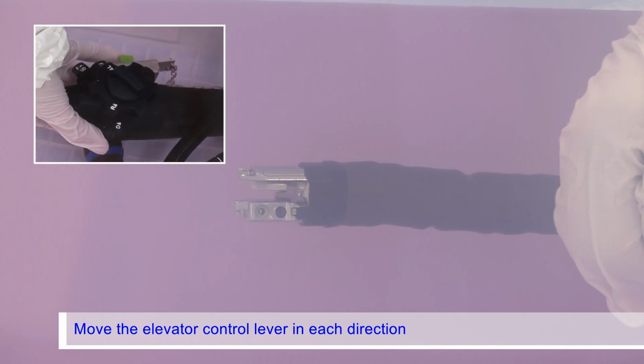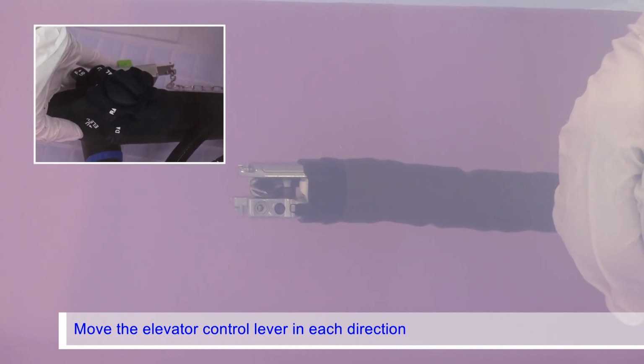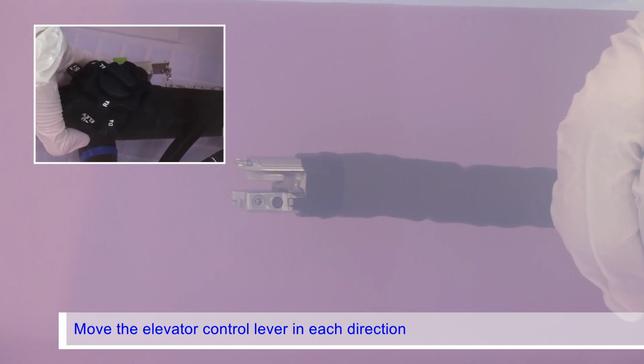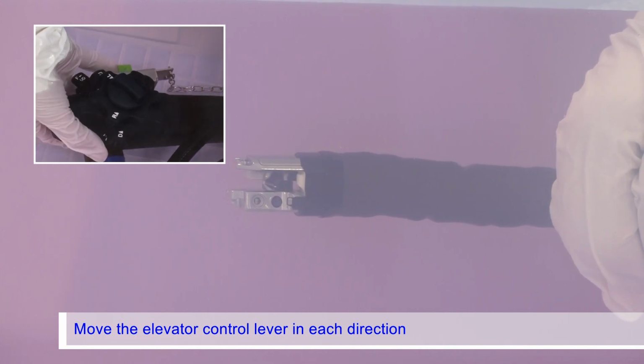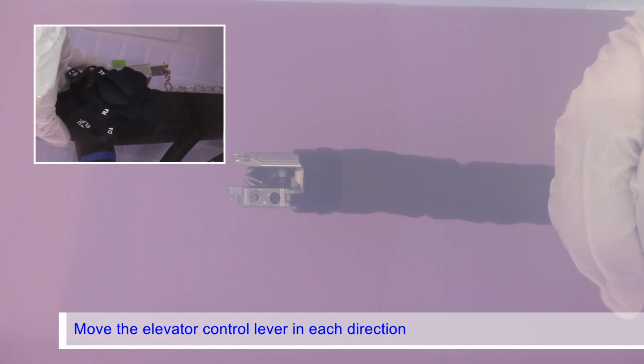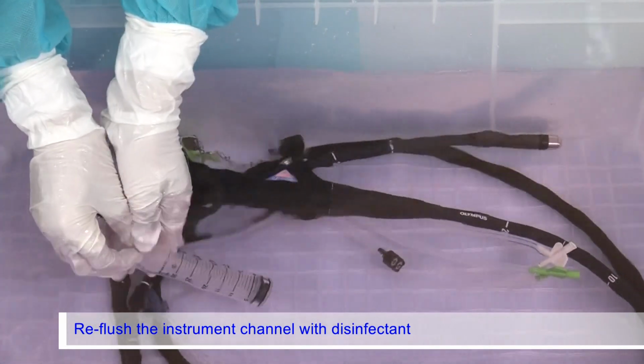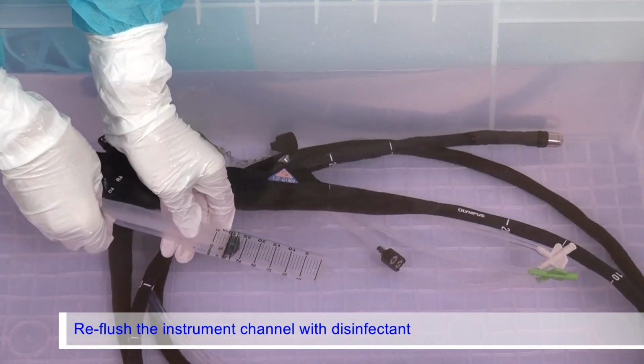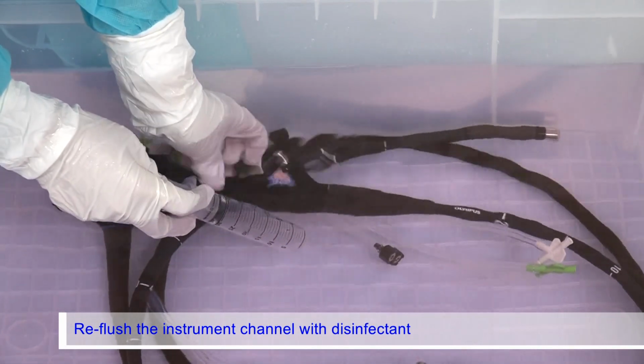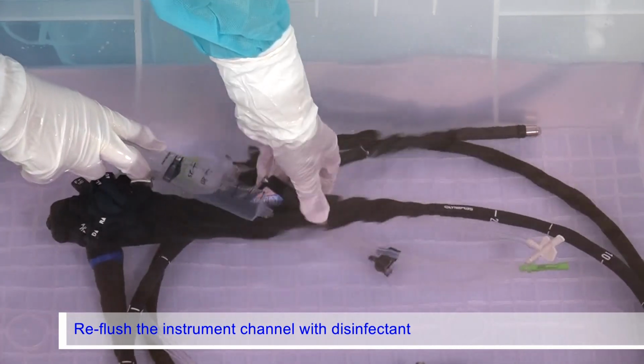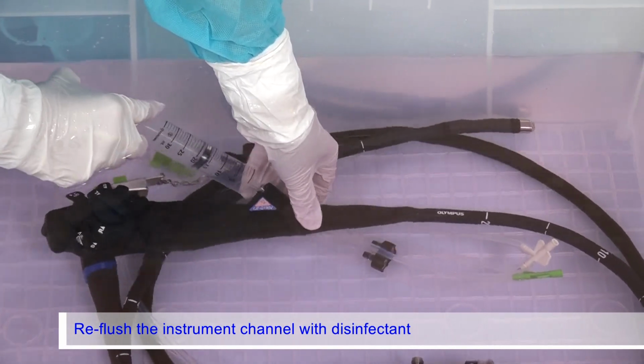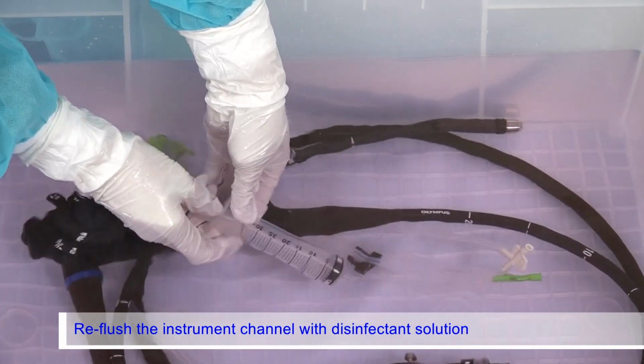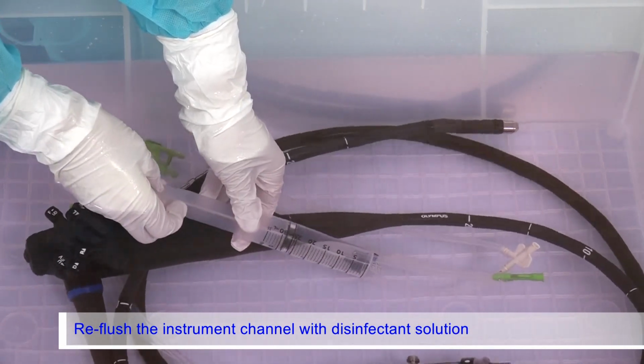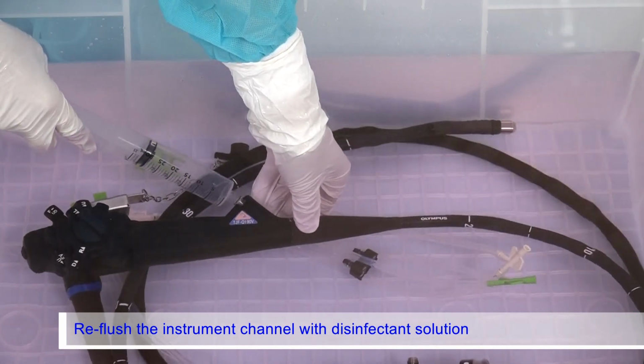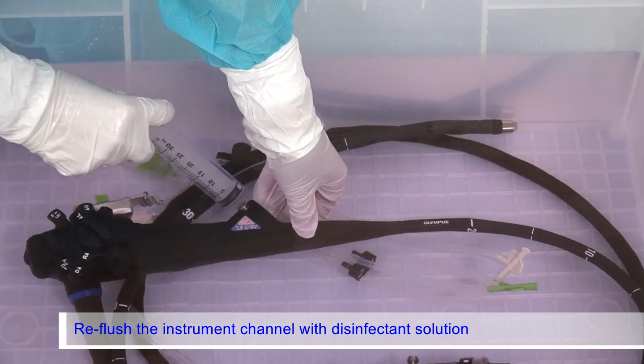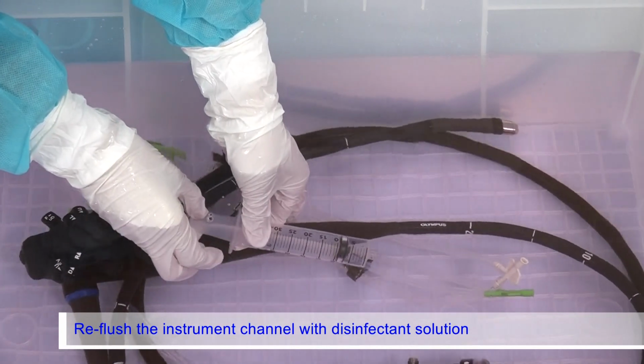While immersing the endoscope completely in the disinfectant solution, move the elevator control lever in each direction 3 times. While immersing the endoscope completely in the disinfectant solution, slowly fill the syringe with the disinfectant solution, put the distal end of the syringe in the instrument channel port, and forcefully flush the instrument channel with 30 milliliters of the disinfectant solution, minimizing disinfectant solution leakage from the port. Repeat the step 5 more times.